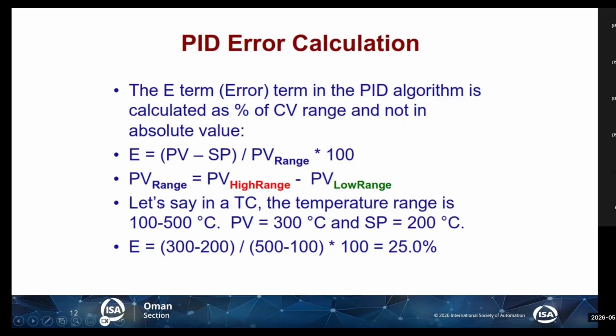And here's an example. Let's say we have a temperature controller, and the range is 100 to 500. Our current process value is 300 Celsius. Our desired set point is 200. From the equation, PV minus SP, that means PV 300 minus SP 200, divided by our range 500 minus 100, which is 400, and we multiply by 100, then we have 25% error. So this is how the PID controller understands it.